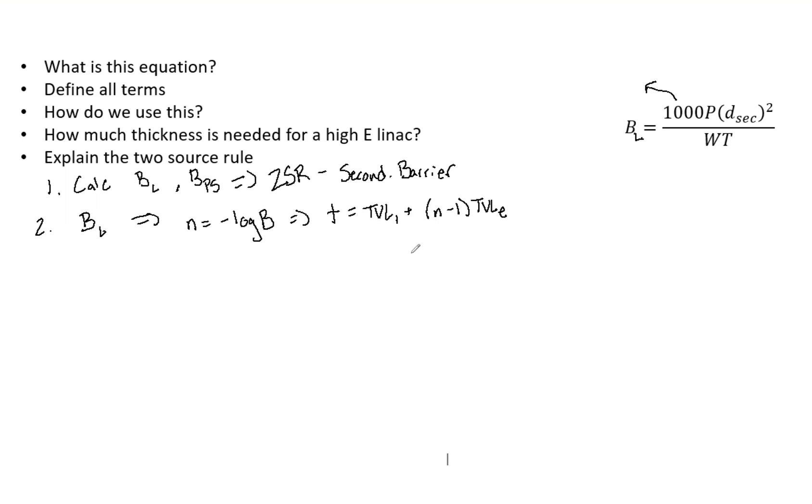So now let's move over to question five here. Explain what the two source rule is. So if you have two different sources, like the scatter and leakage, we're finding the secondary barrier thickness. To compute the TVLs that are needed, you find the TVL necessary for each source. And if that differs by more than one TVL, use the larger TVL. But if they don't, then you add another HVL to the largest TVL. So let me kind of write that down. Hopefully you've seen this before. If so, you can just click off and move on to the next video. If not, let's explain this.